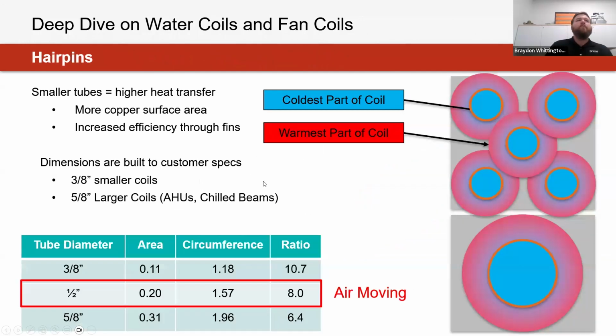And the last one, I'll just touch on briefly, as it's not going to have as much influence, and is more steady state in terms of how these coils are manufactured from an air moving perspective, is just going to be those hairpins and where they're connected. We mentioned earlier that 1/2-inch tubes are more typical and are what's utilized with air moving equipment, for the energy efficiency through those tubes. Tom had mentioned earlier, well, what about 3/8? Commonly we see those on much smaller coils. And for any of you that ask for higher numbers of rows of coil within the system, that's where you might start seeing 5/8 larger coils for some rooftop equipment as well.